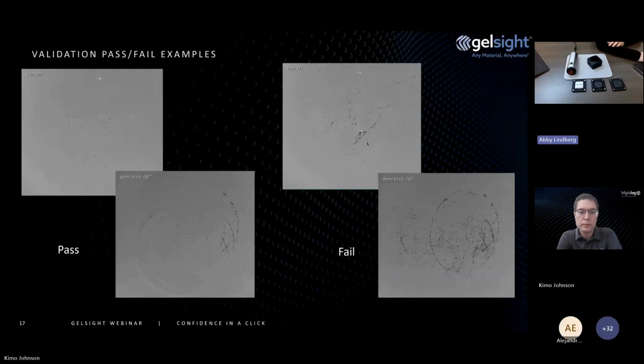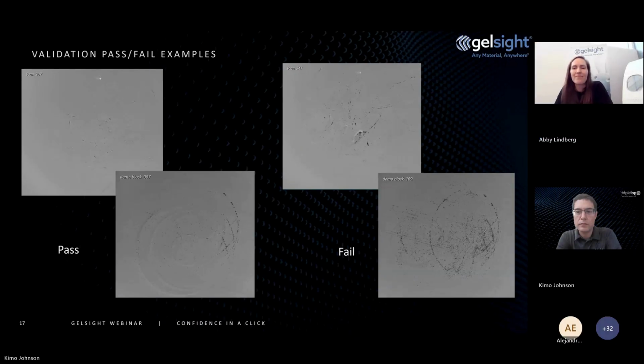I'll also switch my camera back over here. So on the left-hand side of these images, these are ones that have passed validation. So even though you see some damage on the surface of these gels, these are still passing validation. We're still getting measurement results within our tolerances. And on the right-hand side, we're seeing some that fail validation. And you can see there's much more damage. The black or white spots on there indicate light coming through that pigment layer. I know, Kimo, you could talk a little bit about the importance of that pigment layer.